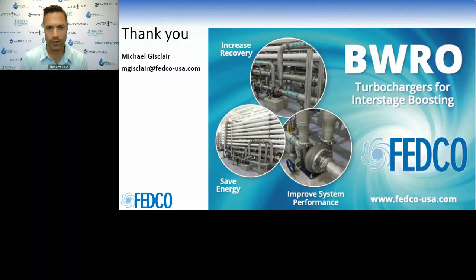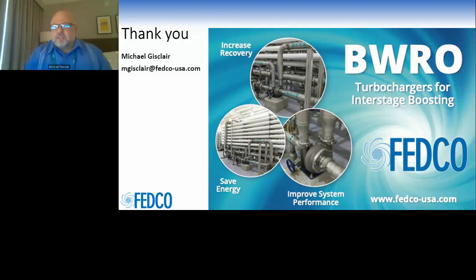Sure. Coming off of that presentation, curious what if I need more interstage boost than available from the brine energy to the turbocharger? Good question. So if you think about a turbocharger essentially as being a single stage centrifugal pump with a rotor prime mover, applying a motor to the turbocharger such that now that pump impeller has two prime movers, you can apply additional energy to that rotor, to that pump impeller, such that you can achieve higher pressures or more consistent pressures than what is available from the brine energy.